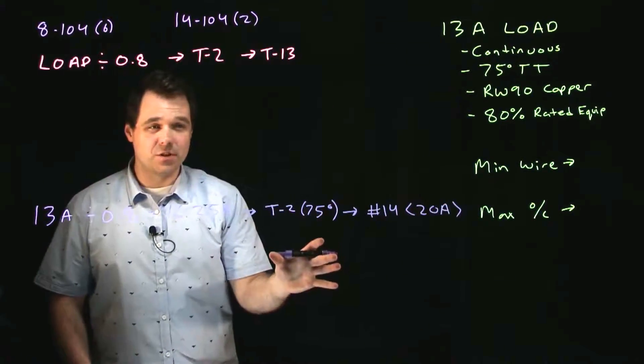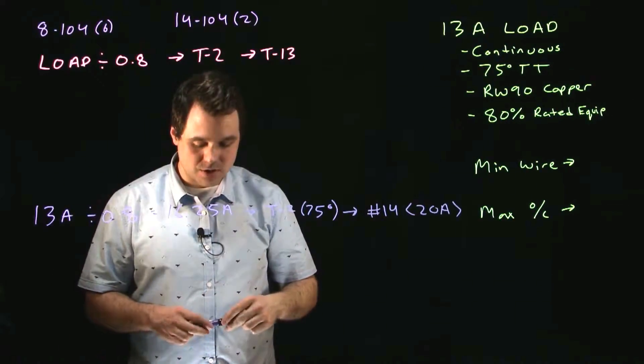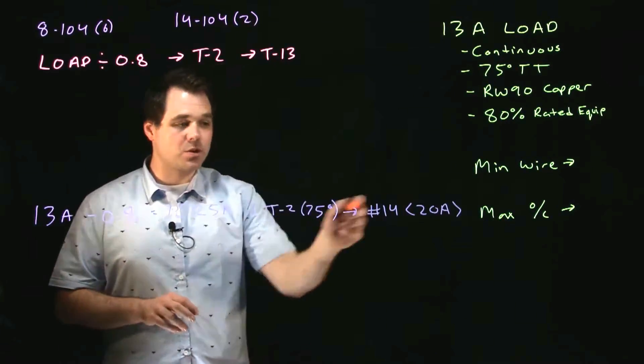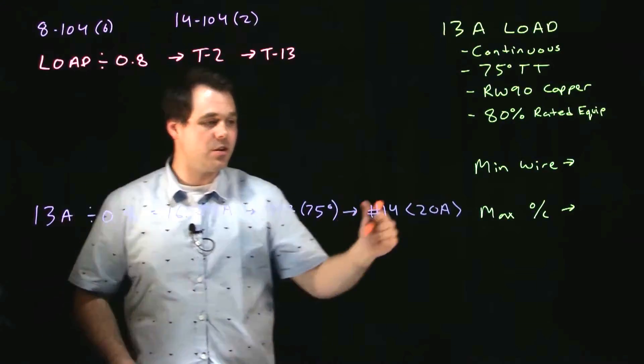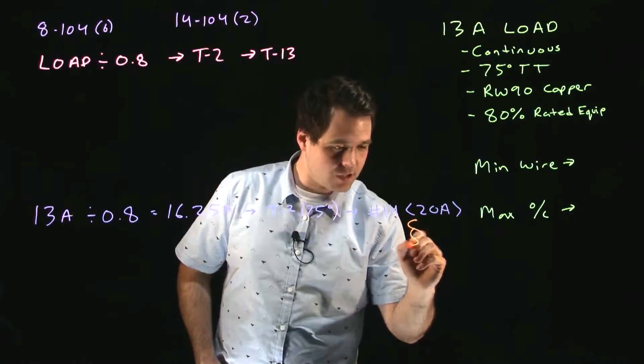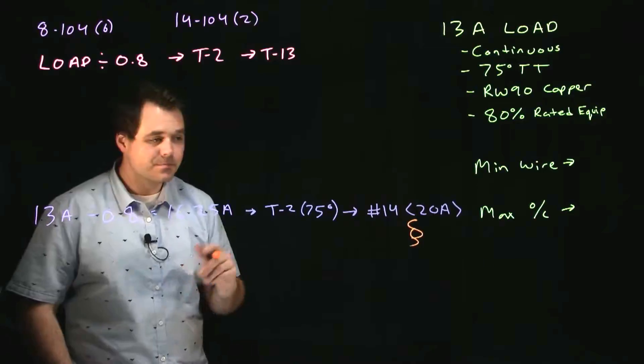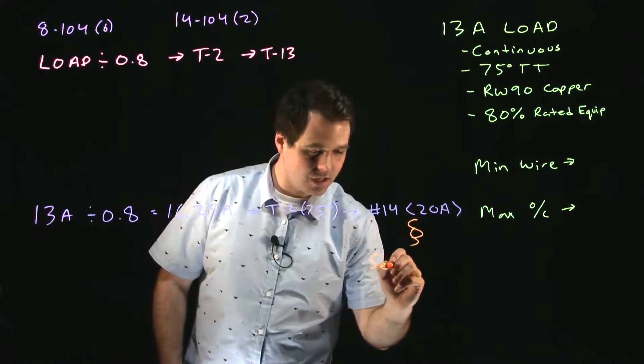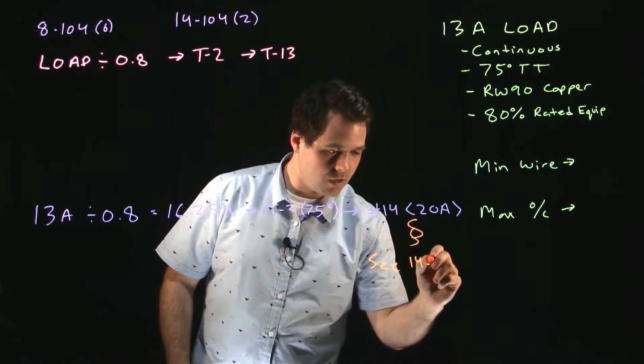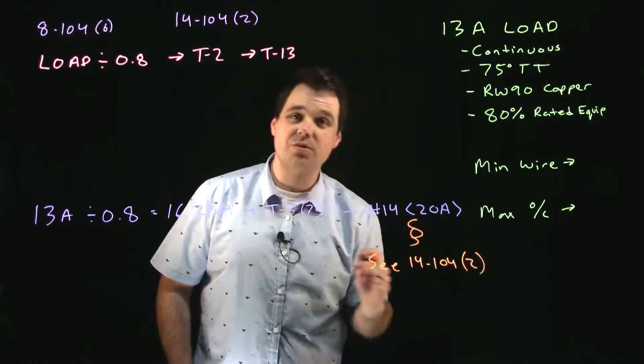Now just because it's good for 20 amps doesn't always mean we get to put a 20 amp overcurrent on it. Right next to 14 number 14 on table 2 there's the little symbol that looks like this, a double S, a squiggle, and it says to see 14-104 sub rule 2.